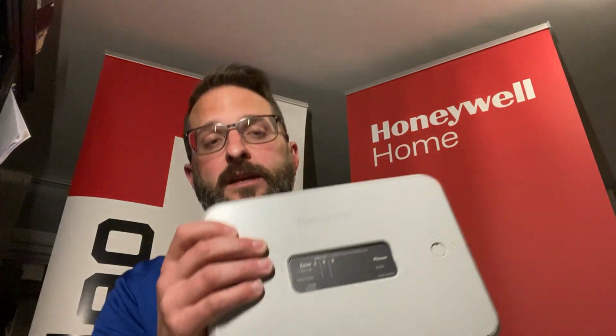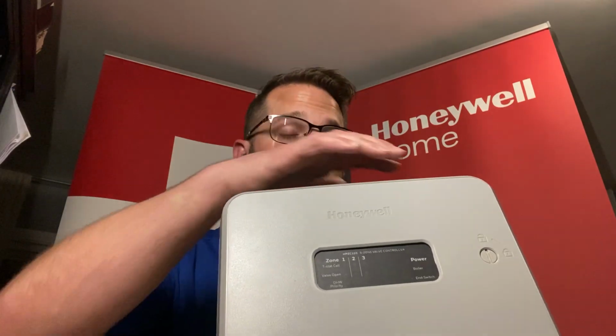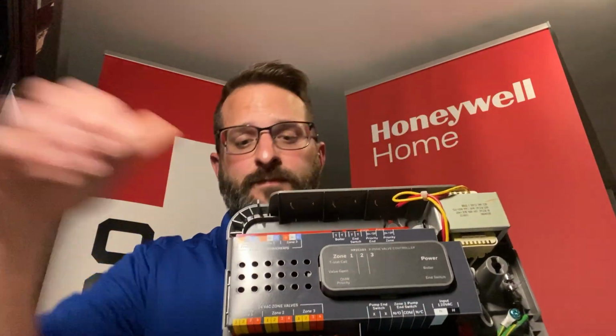So taking a look at it here, we first added a quarter turn cam lock that actually stays with the cover when you take it off. This allows us to put it in a smaller footprint during installation, because the screws aren't on the top or the bottom. It's actually on the front, and then it's less risk because we're not going to be losing any screws or anything because it stays.